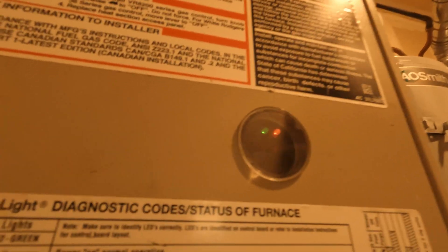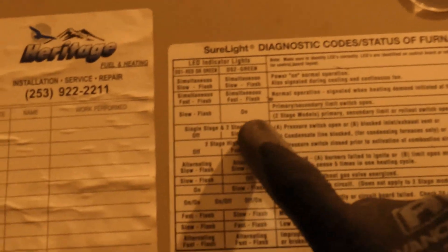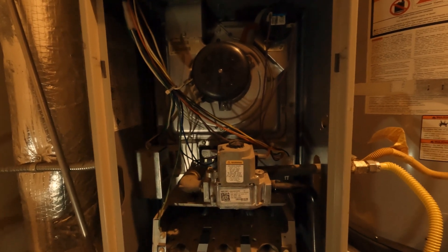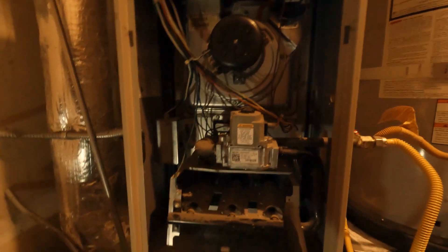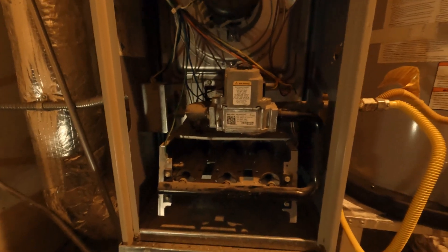Let's turn the circuit breaker back on. Let's check the LED status — that looks good right there. Flash flash flash flash — no more error operation. Let's head inside the house and crank up the heat on the thermostat to activate the igniter.